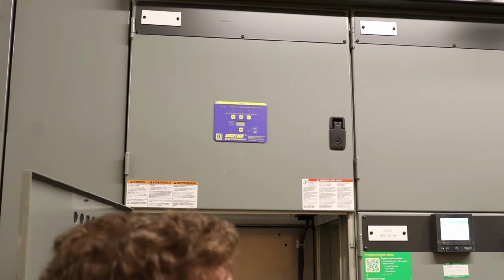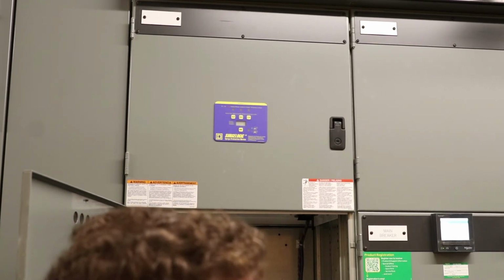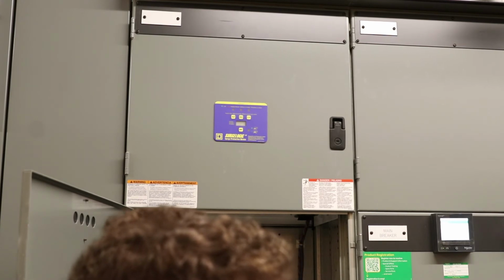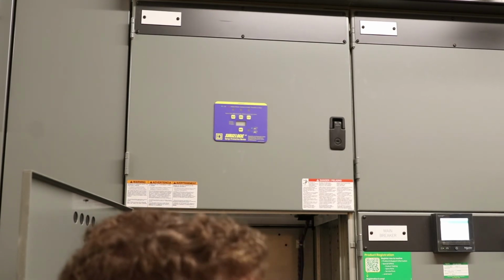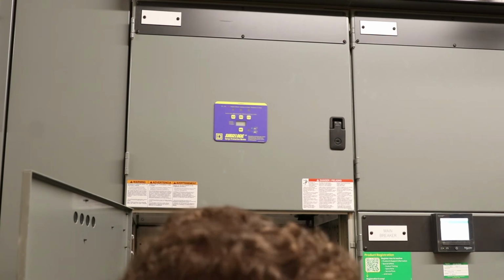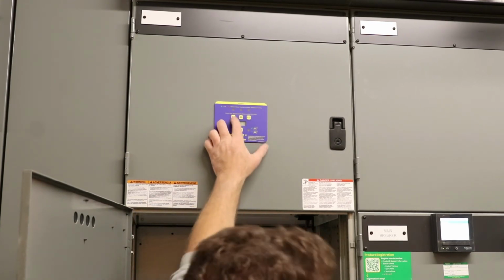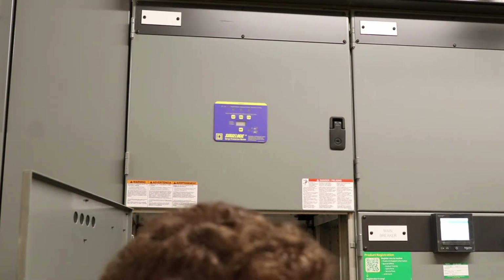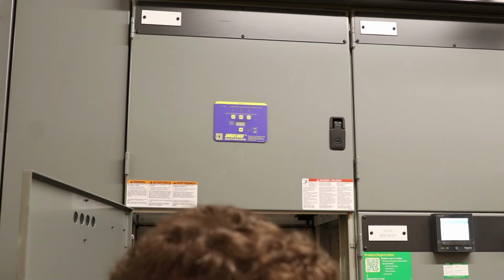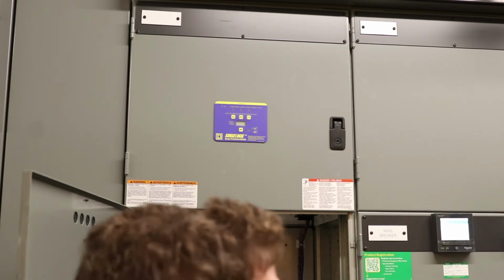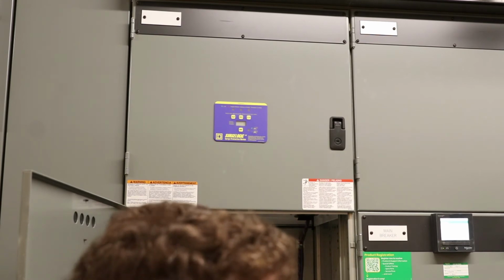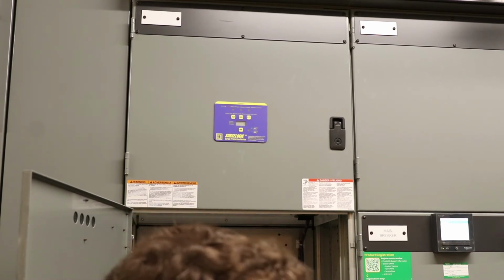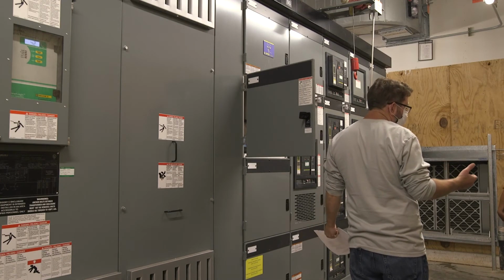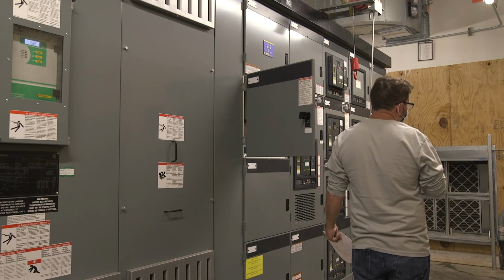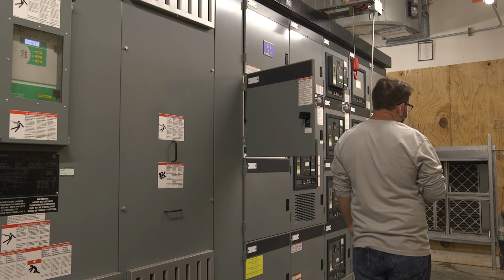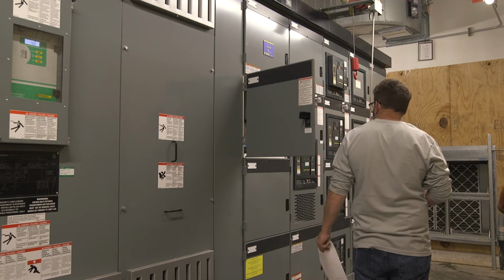Depending on the interrupting rating of the modules, there's either 2 per phase or 1 per phase. Like I said, they're in the back. As long as they both have good health, you'll get a green light for that phase. If you go back and look at the modules themselves, they'll have green lights. If one of the modules were to go bad, you get a red light here. You look on the modules themselves, one might be green, one would be red. One bad module on a phase will give you a bad phase indication out here.